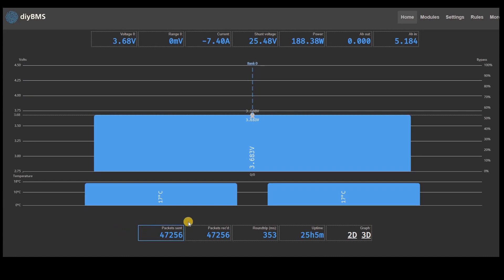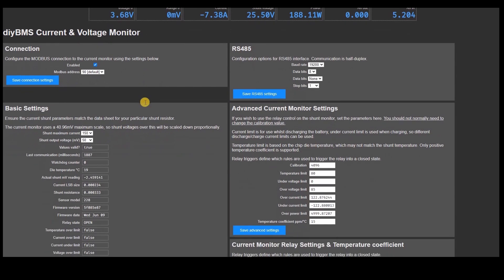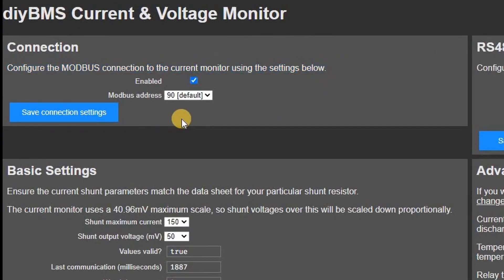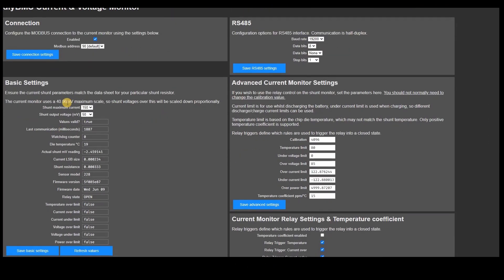With the addition of the new current monitor, several changes to the controller interface were required. The latest version has a new menu option specifically for the current monitor. There are only two sections which are really important: first, you need to enable the current monitor in the Connection section. After this you'll need to specify the size of shunt you have connected — in my case a 150-amp shunt with a 50 millivolt output scale. Other scales are supported, although you'll get the best results using a 50 millivolt shunt.